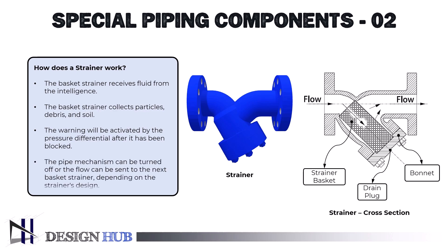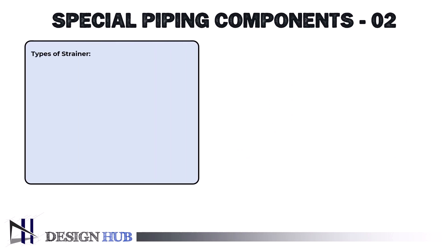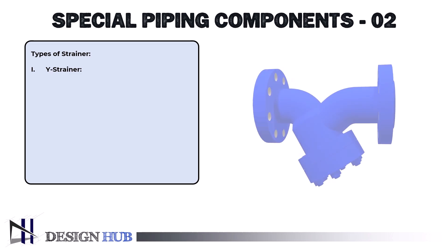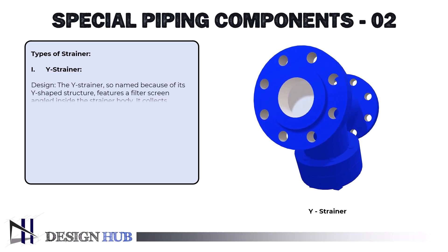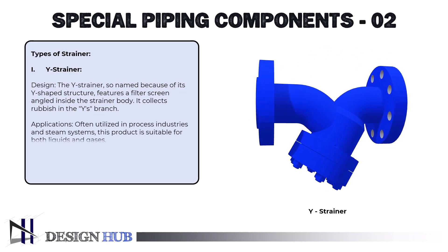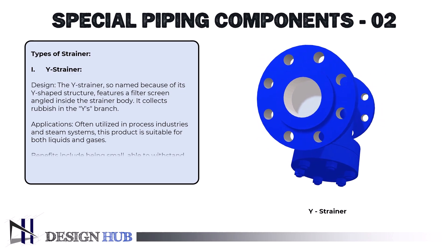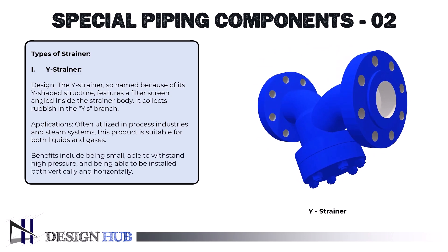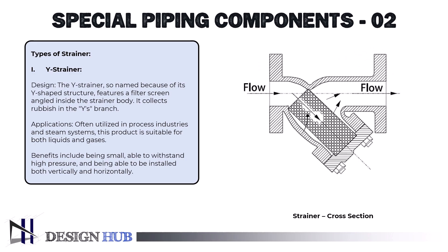Let's go through strainer types. The first one is the Y strainer. The Y strainer, so named for its Y-shaped structure, features a filter screen angled inside the strainer body. It collects rubbish in the Y's branch. Applications: often utilized in process industries and steam systems, this product is suitable for both liquids and gases. Benefits include being small, able to withstand high pressure, and being able to be installed both vertically and horizontally.